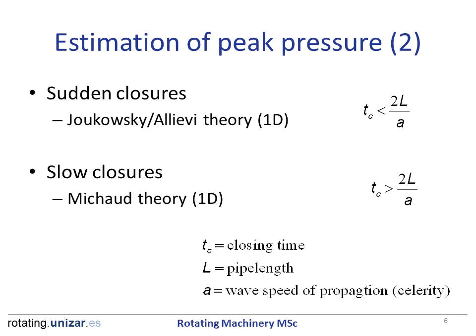To estimate the peak pressure, we have to distinguish two cases depending on whether the change of velocity inside the pipe is sudden or slow. Sudden closures are those in which the closing time is smaller than the wave's propagation and return time. In this case, the peak pressure is estimated according to the Joukowsky-Alievi theory. If that condition is not met, the closure is slow and the peak pressure can be estimated according to Michaud's theory.